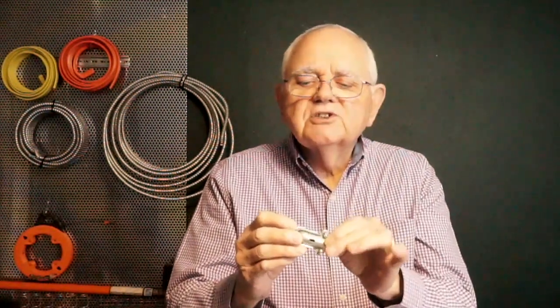Well, it's got to be identified for use. It doesn't have to be on the fitting itself, right? It could be on the smallest container that it comes in, whether that be a plastic bag, or if I'm buying 100 or 200 of them at a time, that would be on the box itself. So it's kind of interesting. Let's take a look at, for instance, here it says dry locations only on it. It's got the UL label. This is a 90-degree fitting then. Other than that, there's not much information on there. So I have to look at the container that it came in.